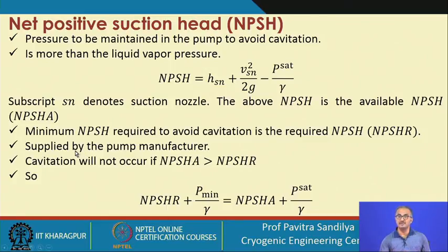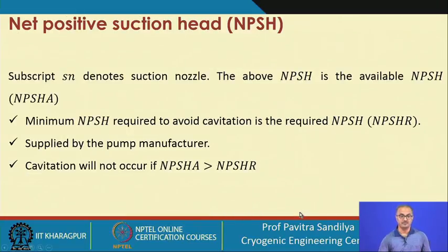NPSHR is the minimum NPSH needed to prevent cavitation, and the actual available NPSH (NPSHA) must be greater than NPSHR. Generally the NPSHR value is given by the manufacturer and the relationship is: NPSHR plus P_minimum divided by gamma equals NPSHA plus P_SAT divided by gamma. The available NPSH (NPSHA) must always exceed the required NPSH (NPSHR) to ensure safe pump operation.